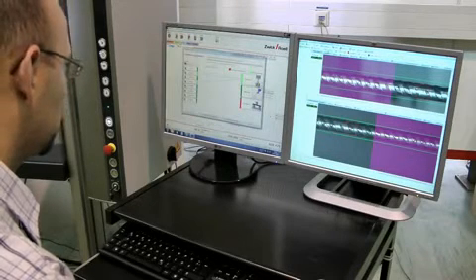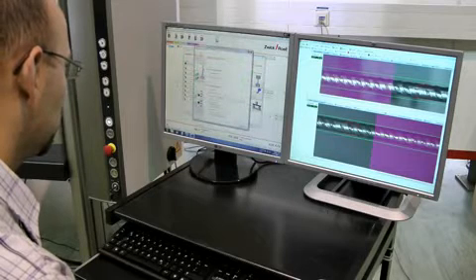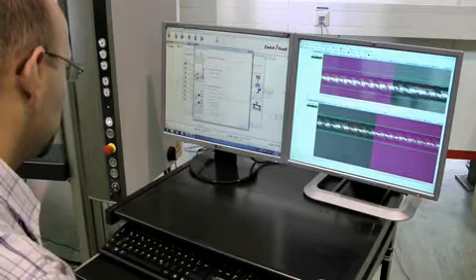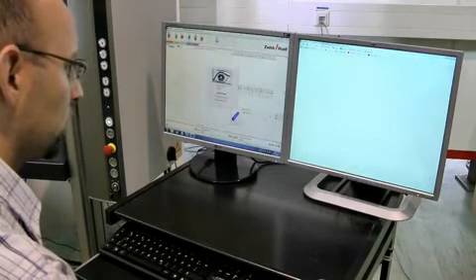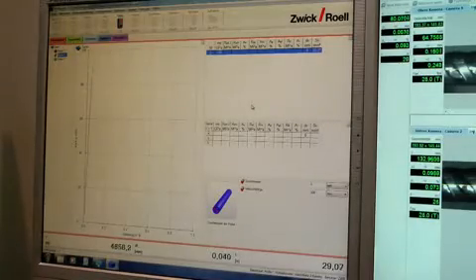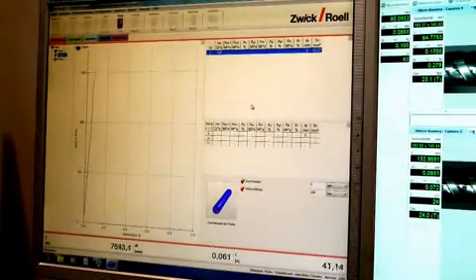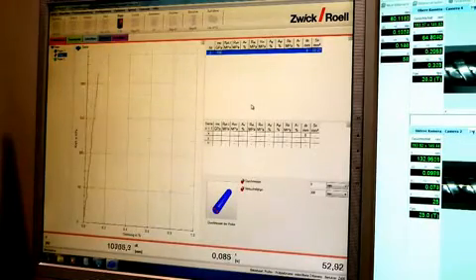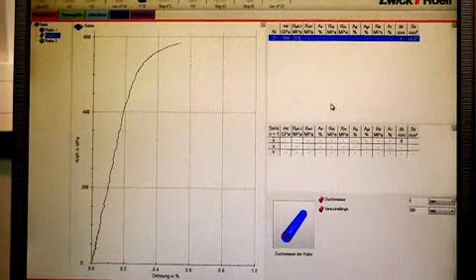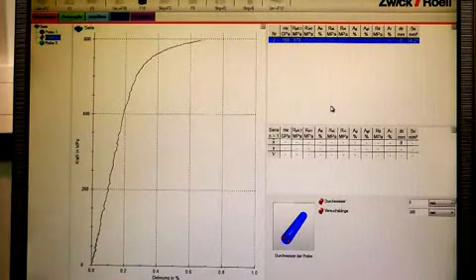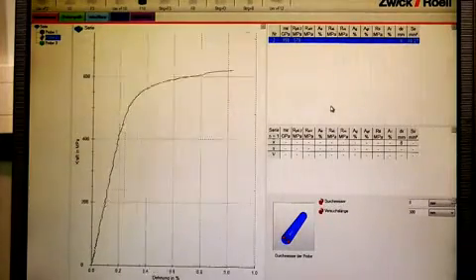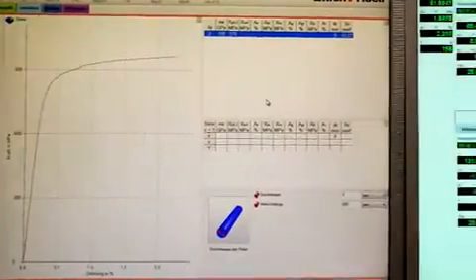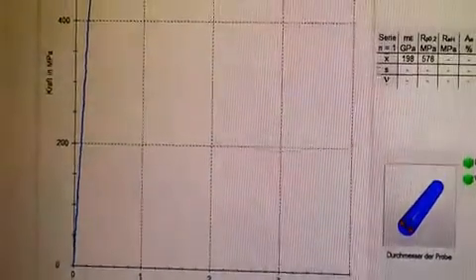The biggest problem of rebar steel tests is that we want to do a test according to norm and the diameter of the rebar steel is very often very small. So with an A5 or A10 test we have a very short gauge length. Compared to the big length of the rebar steel we got a very small gauge length. So it's very likely that the break is outside of our gauge length and the breaking strain cannot be determined correctly at the end of the test.